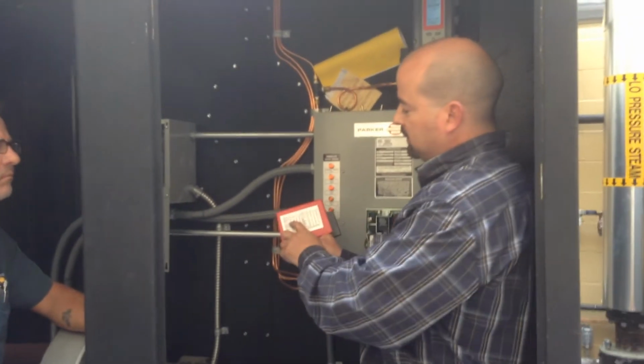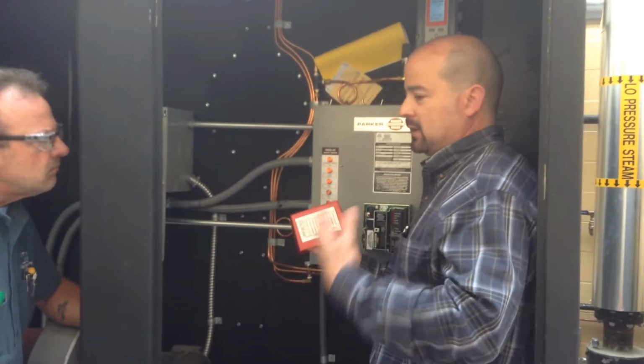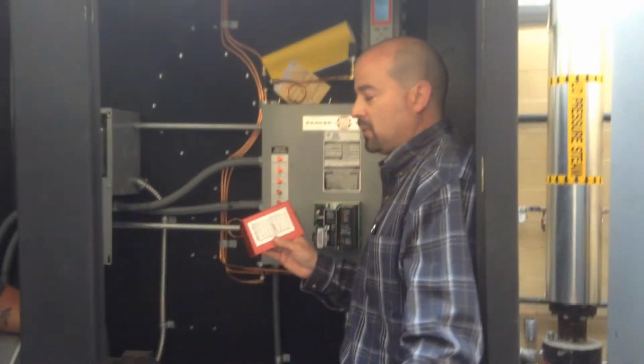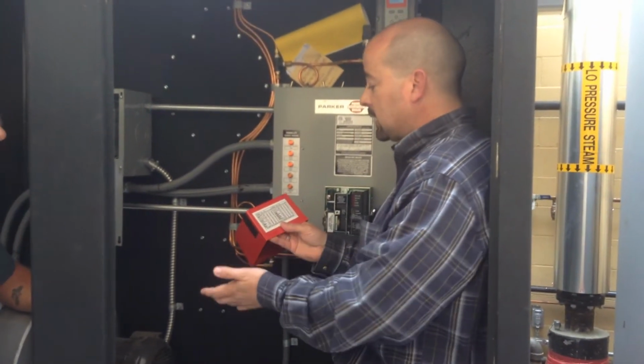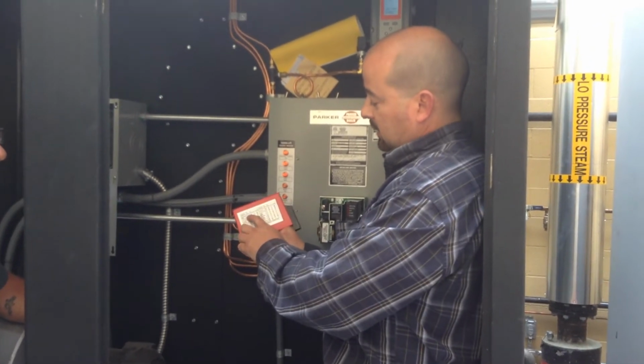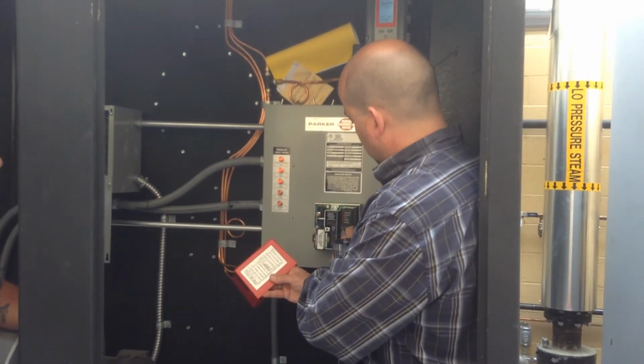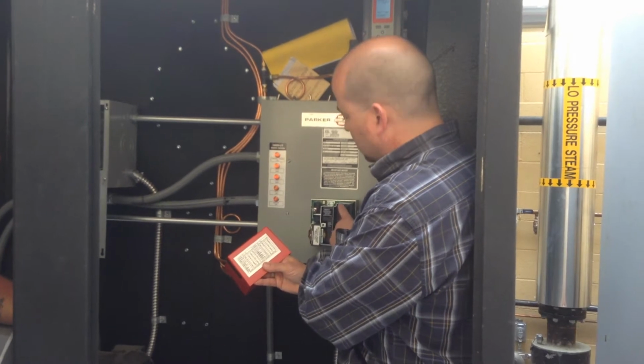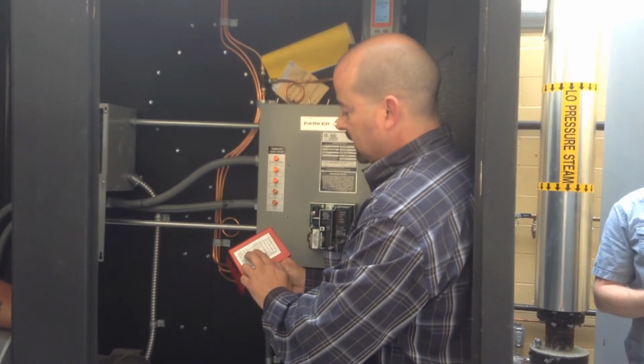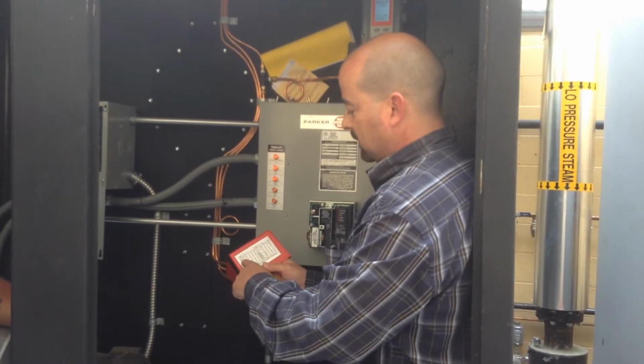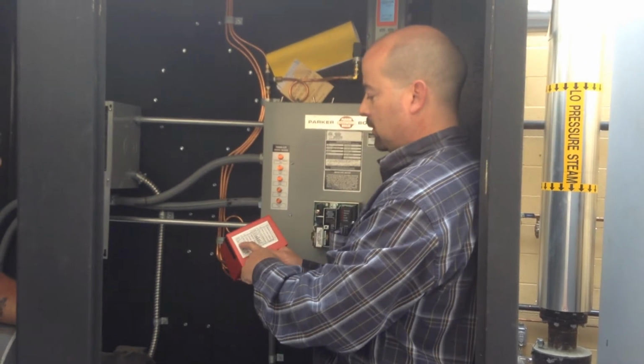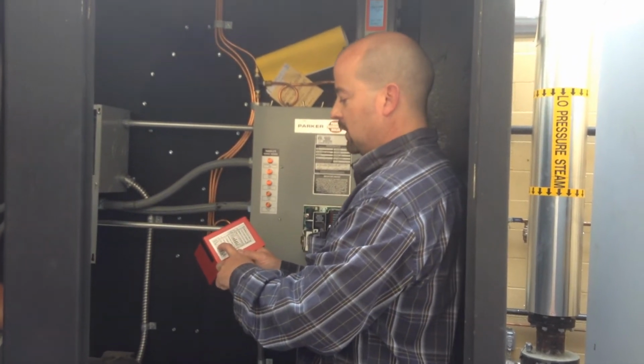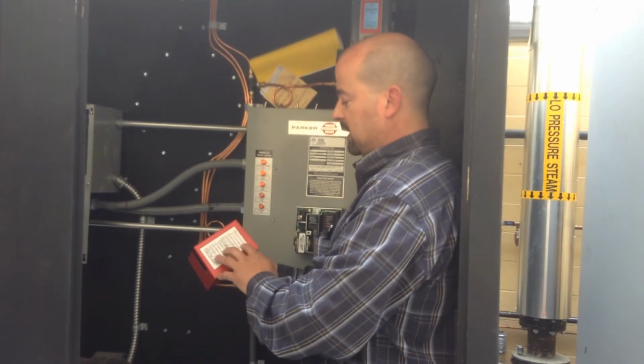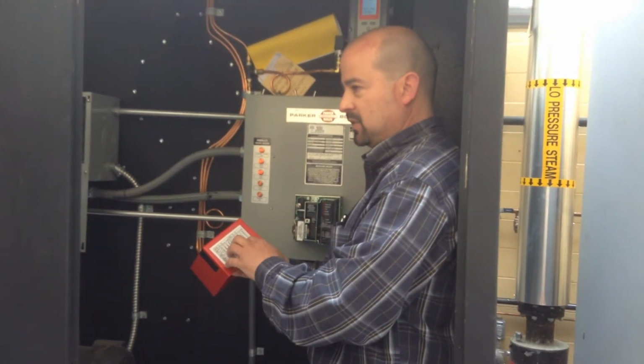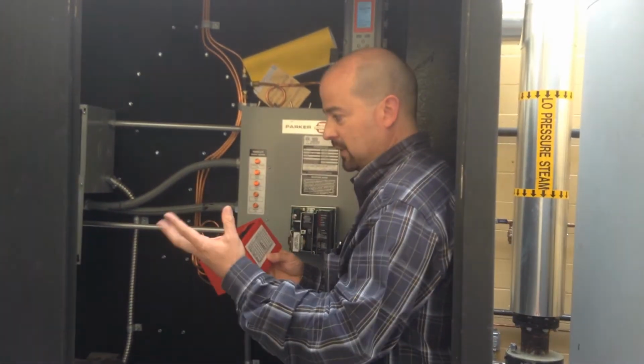But it also gives you some flashing indications. So let's say the boiler flame fails because there's no gas, then it'll lock out, and let's say these 2 lights are flashing, so the lights are right here, so the 2 outer lights would be this code right here, so that tells you line frequency noise or flame failure for PTFI, which is pilot trial for ignition. It's basically just a simple way to see why it failed in flashing lights.